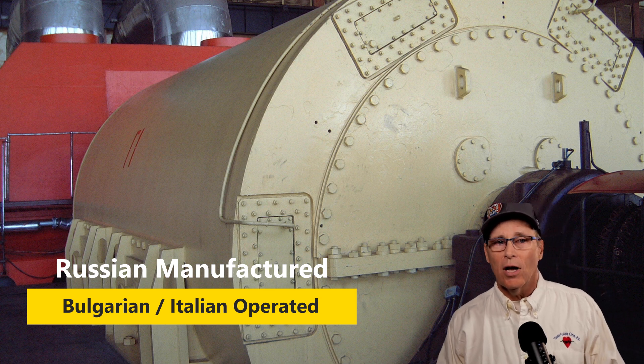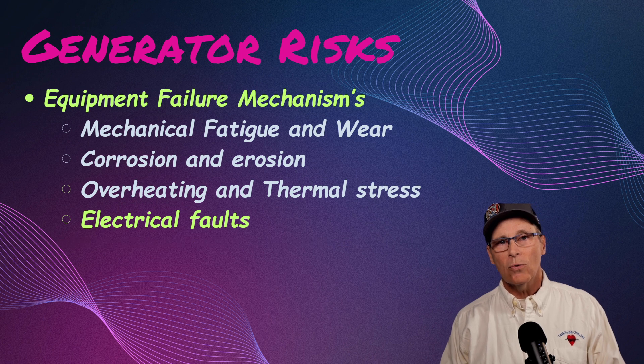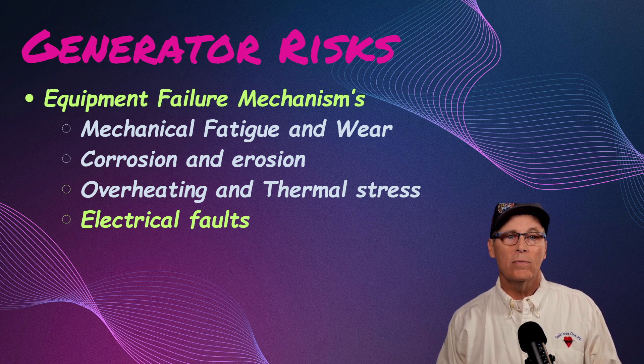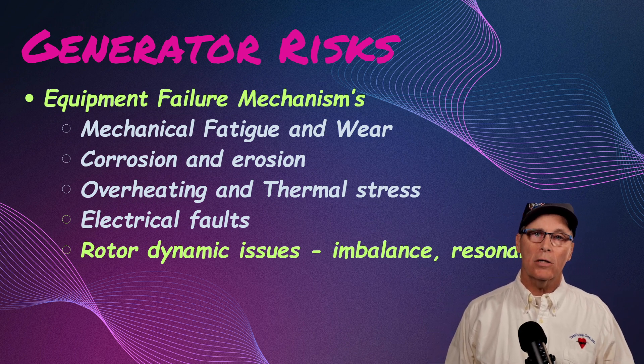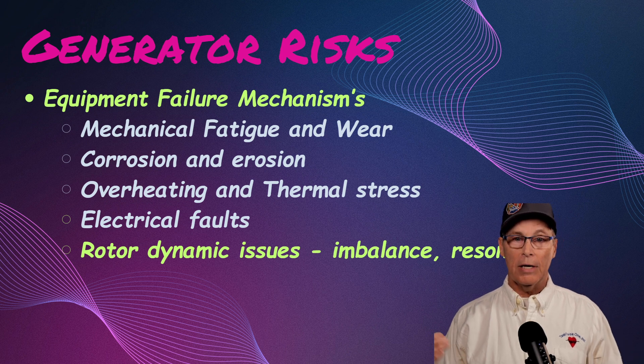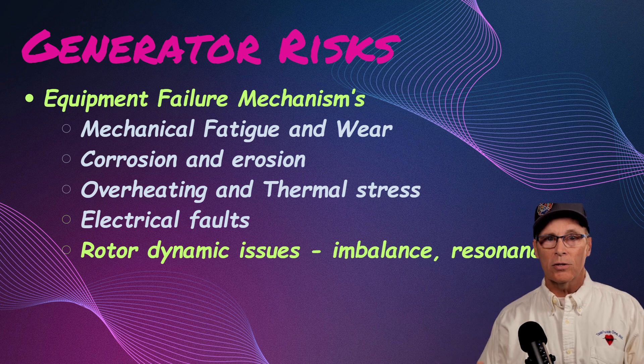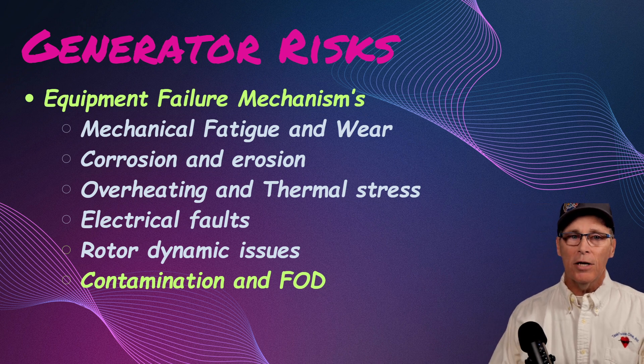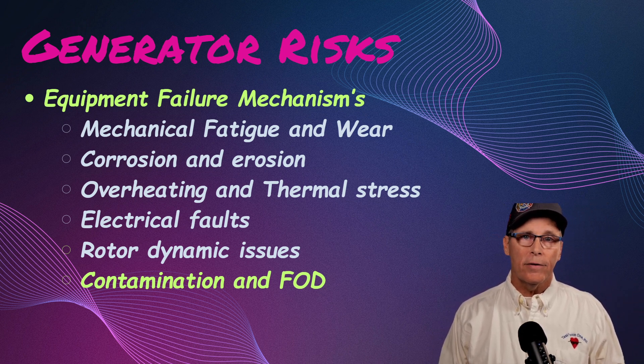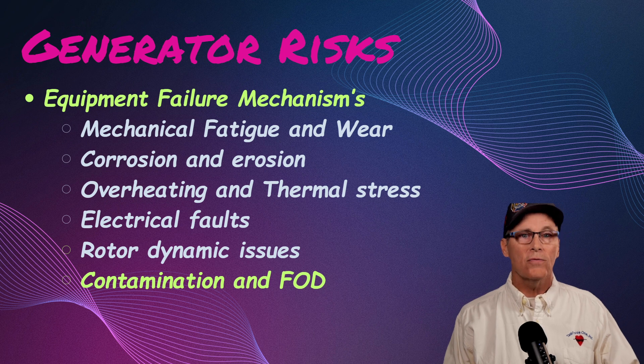This is a large power generator. Electrical faults we've discussed include shorted end turns. Dynamics issues — imbalance, or rotors in resonance at a frequency that stimulates higher vibrations than normal at typical operating speeds. Contamination and foreign object damage — if you're breathing in a lot of air to cool the generator and that air isn't clean, you contaminate the inside, building up the chance for short circuits.